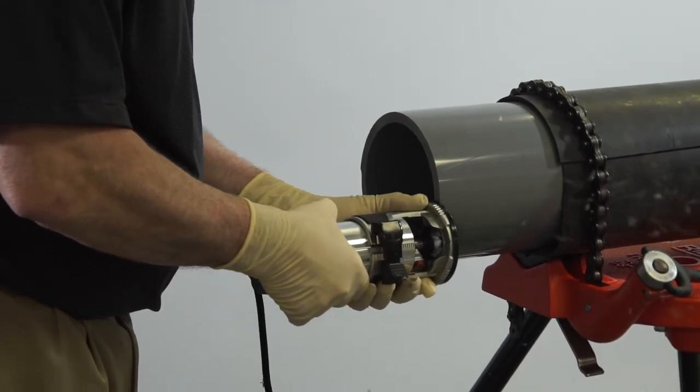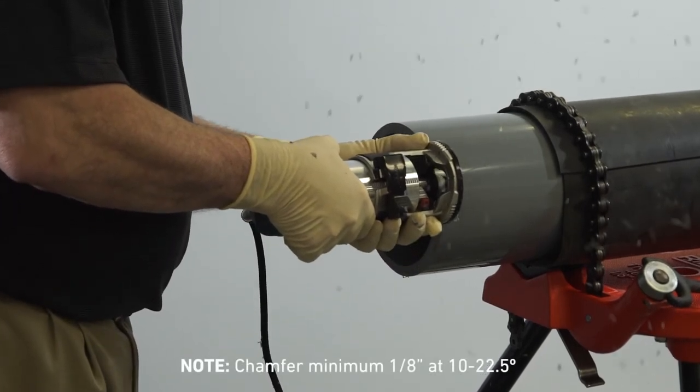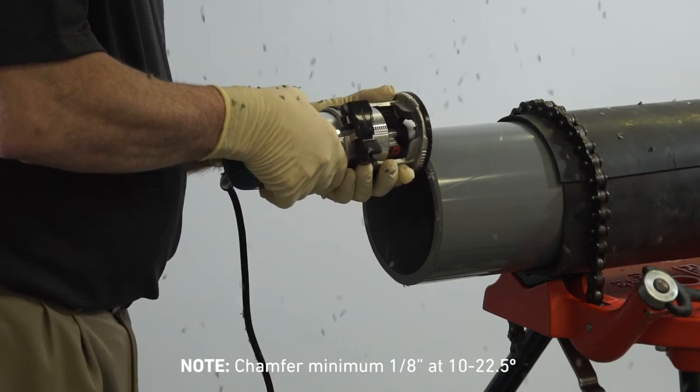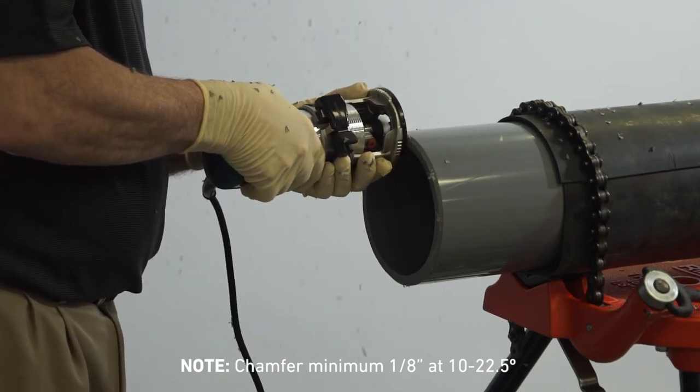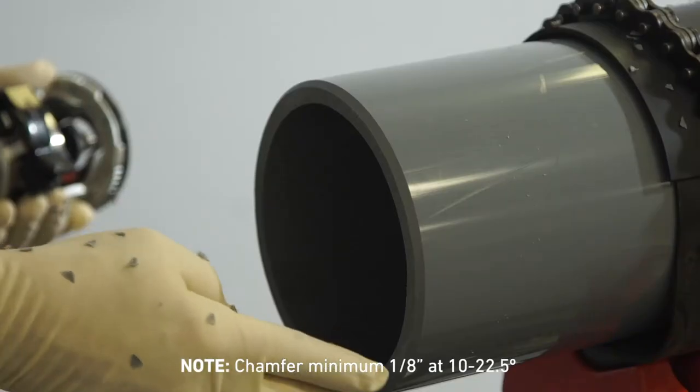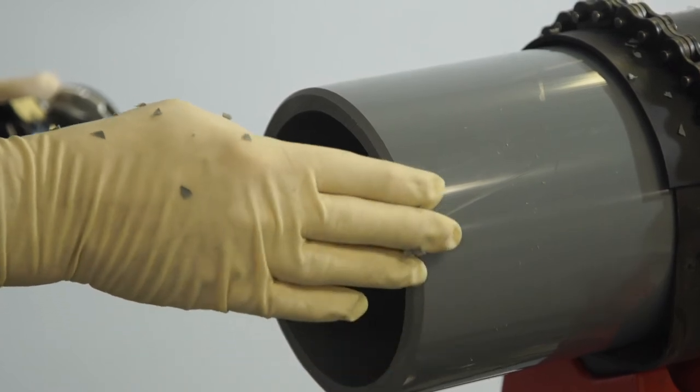A 10 to 22 and a half degree chamfer with a minimum width of one-eighth of an inch must be placed at the end of the pipe to ease insertion of the pipe into the fitting socket. This chamfer will minimize the chance that the edges of the pipe will wipe away the solvent cement or will scrape softened material surface from the fitting socket during the insertion of the pipe.